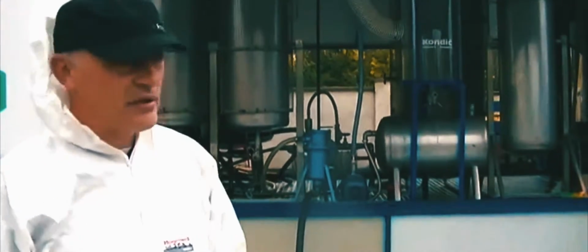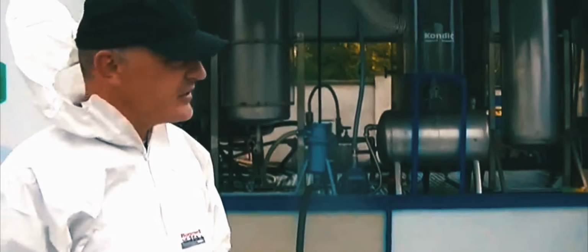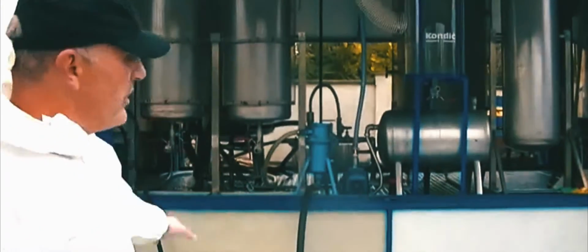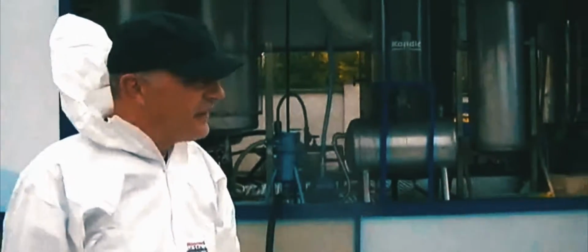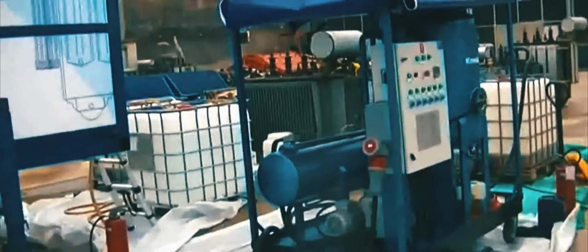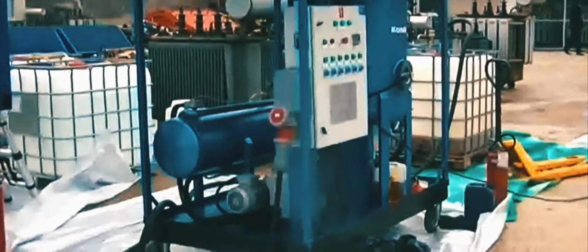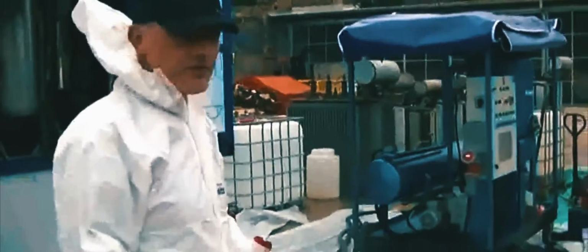After removing those remaining chemicals, we transport the oil to this unit over here, where we do filtration and removal of water. That's a typical unit seen all over power stations for conditioning of oils, where you remove mechanical particles or water present above the level which is safe for usage.